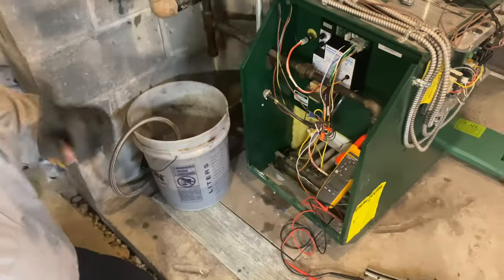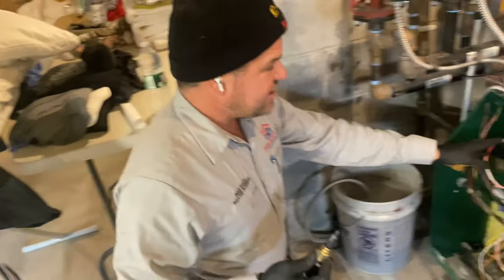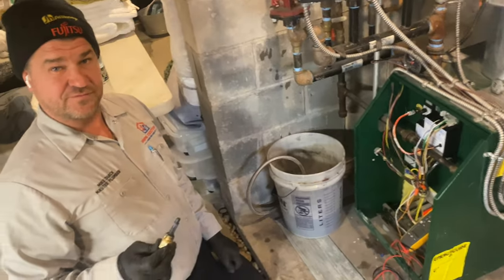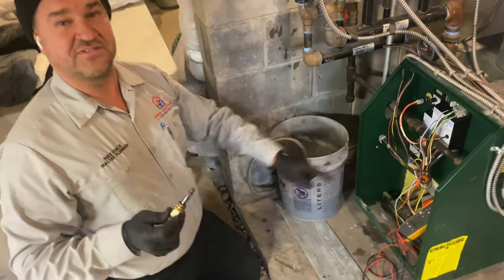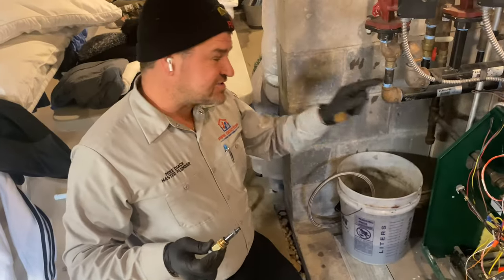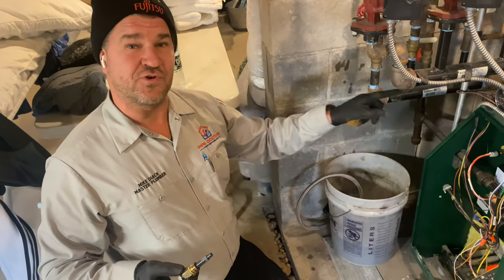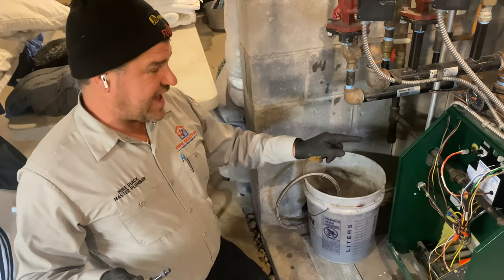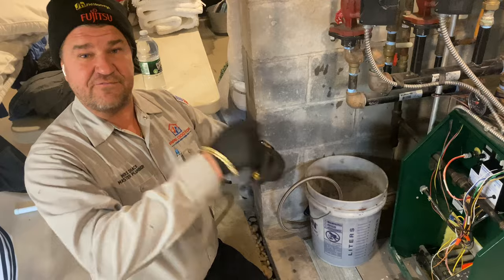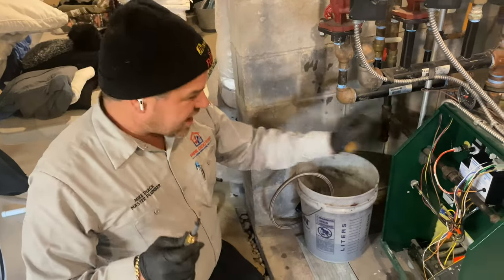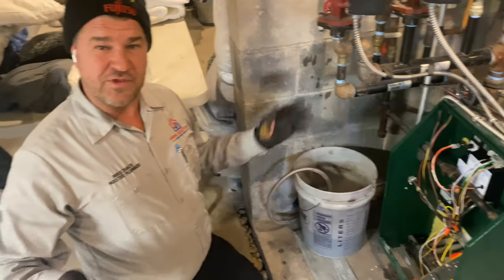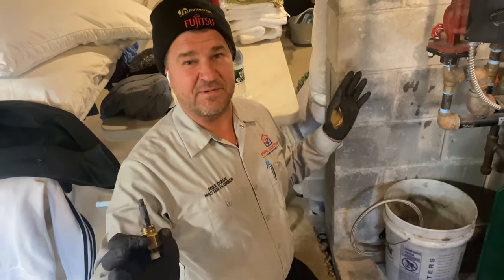What you will see in the field, though, is when you replace a low water cutoff, you will find Teflon tape on it. I'll find Instagrammers and YouTubers and people on social media, plumbers, actively wrapping Teflon tape on the probe right before they put it onto the boiler, and I'm the only one commenting. This is why some people don't like me, because I tell it like it is.